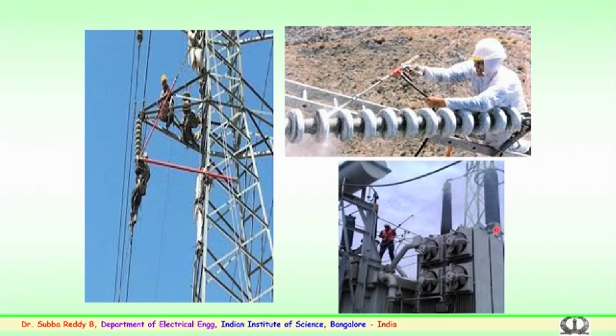This is one more example, in the substation, where the bushing of the equipment, it could be a current transformer or a lightning arrestor, the bushing of the ceramic disc is being maintained and cleaned using a handheld water jet. So, various methods are suggested for cleaning during the de-energized condition. These are a few of the practical methods being employed.